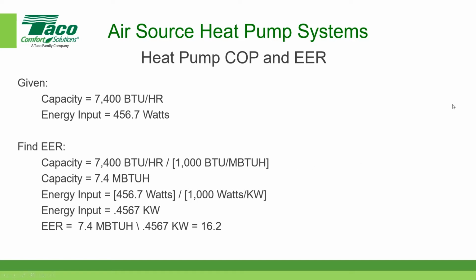And here's a little interesting fact. If you take the EER, which we just calculated in this little example here, the EER is a weird number, but it's one that we use in the industry. It's essentially the BTUs divided by the kW, or MBTUs. EER is actually equal to the COP times 3.412.